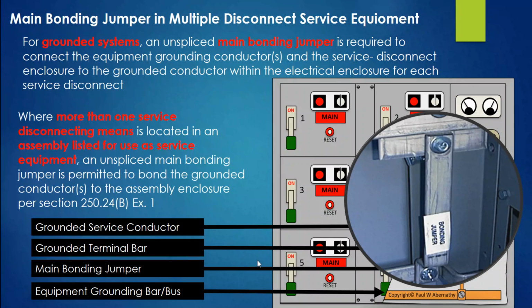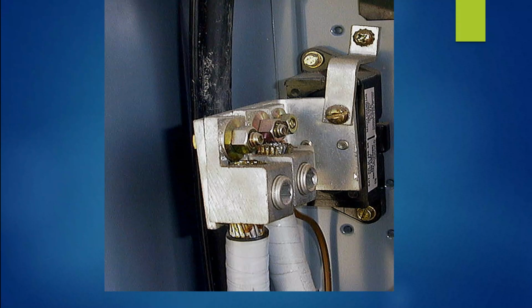Now, this is an example of where you might have those two buses connected together using an actual factory-supplied strap. And this is what you see here. This is the main bonding jumper that's connecting the neutral terminal bus over to the equipment grounding bus or bar. And again, this one will be factory, and you don't need to resize this. This has already been determined by the manufacturer in their testing when they got the listing of this equipment. Here's an example of a strap, again provided by the manufacturer, that's connecting both the grounding conductors and, it looks like, the grounding electrode conductor and the metal enclosure all together. You'll have the literature that says where this strap goes and how you make this connection, and that is all again supplied by the manufacturer.